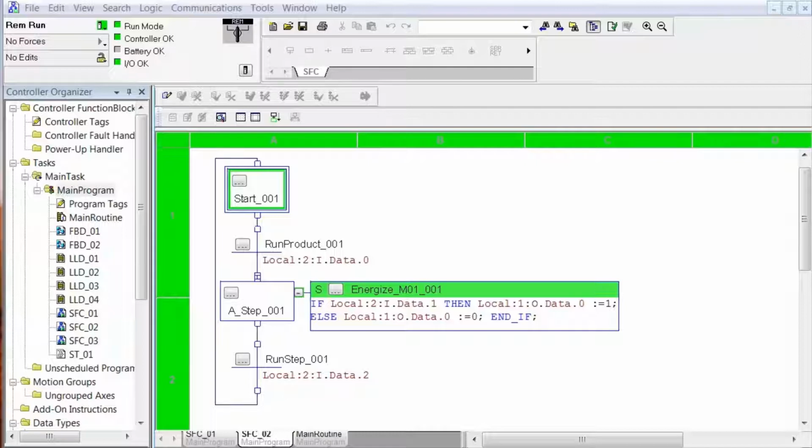You start it and it stays until you hit stop. That's how you would do a stored. So stored, sealed in, and you can do this with regular program control in ladder 500. With RSLogix 500, you just have to use the conventional start-stop logic that you would use with a push button to run a motor, only use it on your JSR.